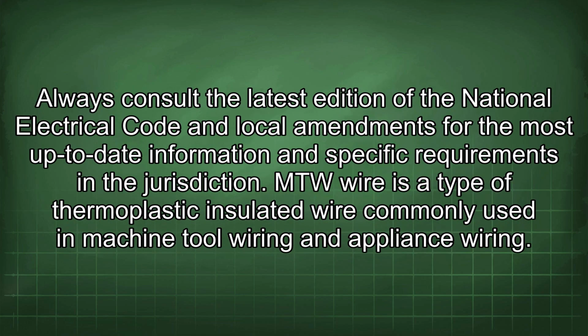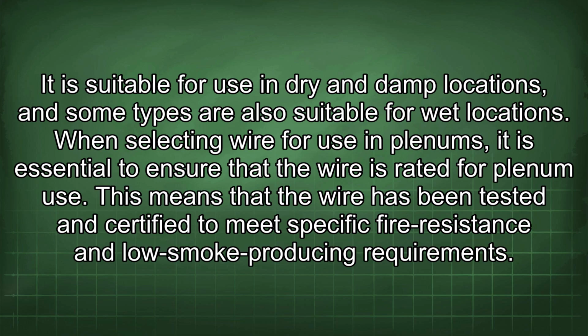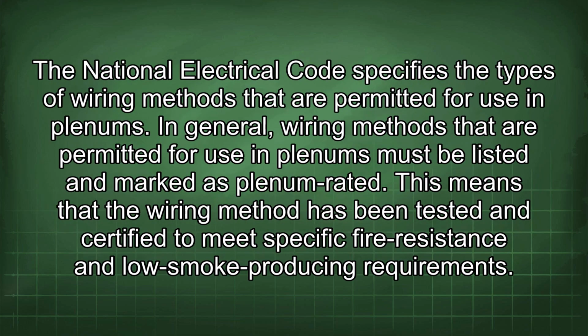Always consult the latest edition of the National Electrical Code and local amendments for the most up-to-date information and specific requirements in the jurisdiction. MTW wire is a type of thermoplastic insulated wire commonly used in machine tool wiring and appliance wiring. It is suitable for use in dry and damp locations, and some types are also suitable for wet locations. When selecting wire for use in plenums, it is essential to ensure that the wire is rated for plenum use. This means that the wire has been tested and certified to meet specific fire resistance and low smoke producing requirements. The National Electrical Code specifies the types of wiring methods that are permitted for use in plenums.